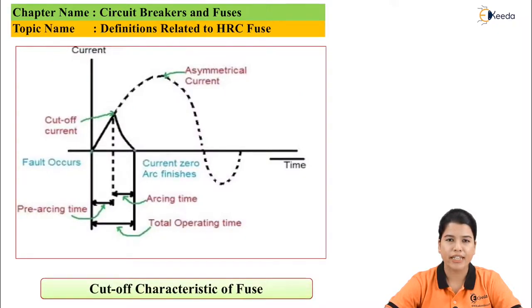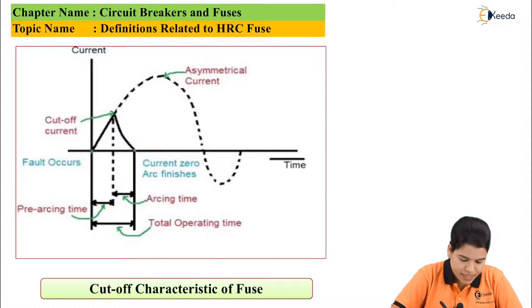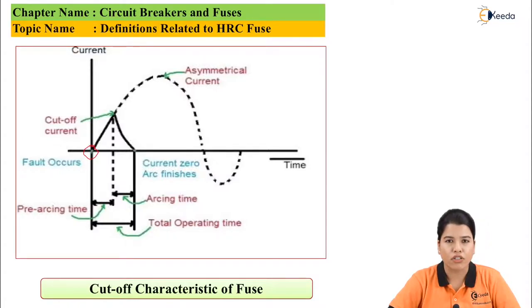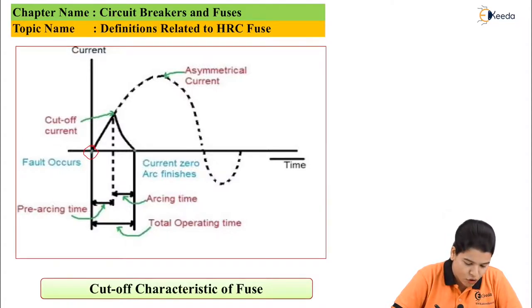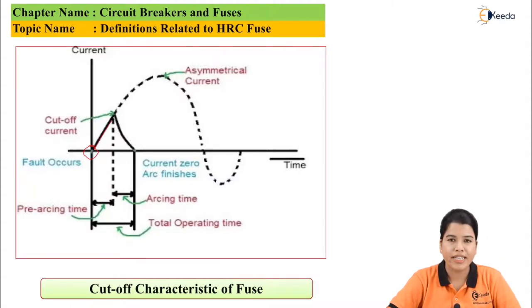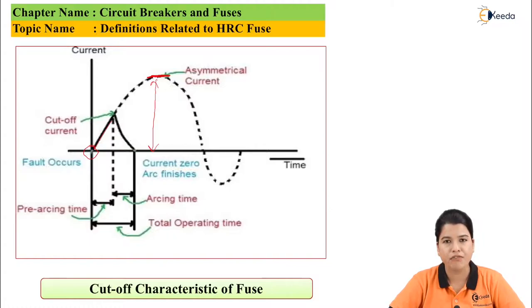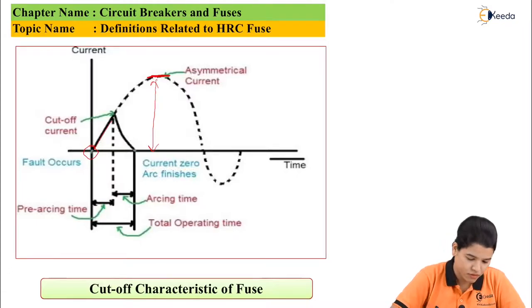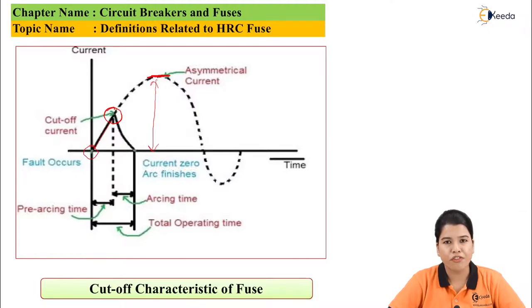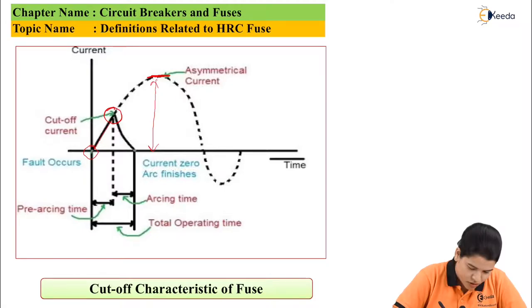The figure shows the cutoff characteristic of the fuse. This is the point at which the fault occurs, and from here the fault current starts rising. This peak value of current is the prospective current — that is the current which would have flown through the system if the fuse was not present. This is the cutoff current, which does not allow the fuse current to reach its prospective peak.